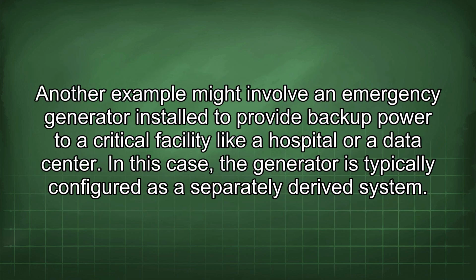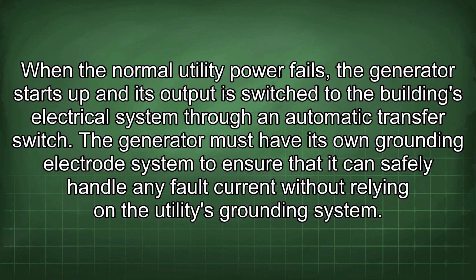Another example might involve an emergency generator installed to provide backup power to a critical facility like a hospital or a data center. In this case, the generator is typically configured as a separately derived system. When the normal utility power fails, the generator starts up and its output is switched to the building's electrical system through an automatic transfer switch. The generator must have its own grounding electrode system to ensure that it can safely handle any fault current without relying on the utility's grounding system.